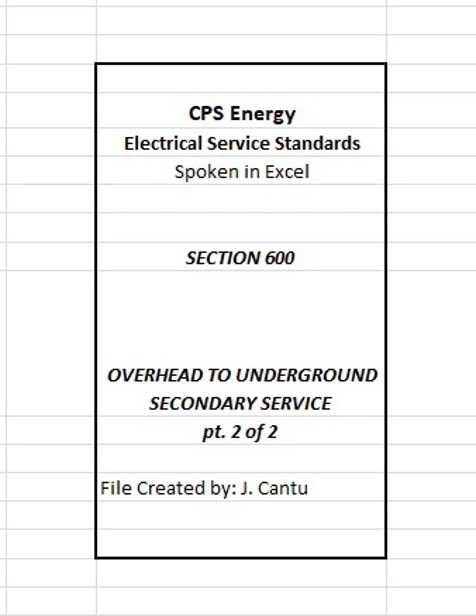604.13 Backfill provisions. Materials used to backfill a trench shall be clean and free of sharp objects. Customer shall be responsible for backfilling service lateral conduits in accordance with CPS Energy specifications.